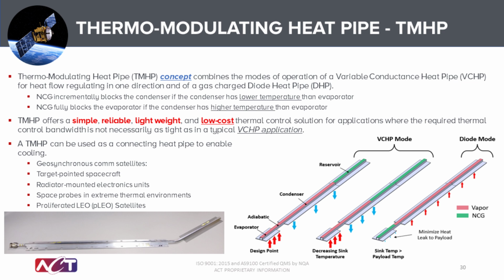So the first of those three images shows a relatively well open condenser for direct heat transfer as needed. Now, if the sink temperature goes down, more heat tends to be sucked out from the evaporator. Then the front, generated by the non-condensable gas, advances upstream, blocking more of the condenser. In other words, increasing thermal resistance and minimizing the fluctuation of the heat source, which is the evaporator.